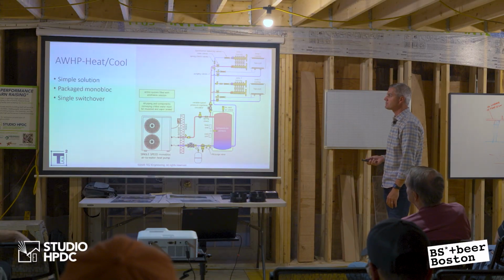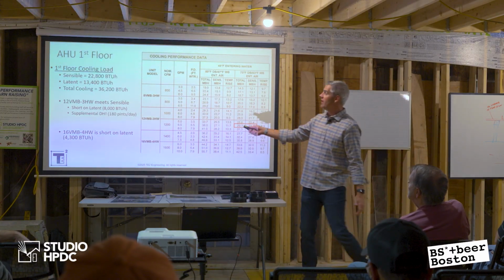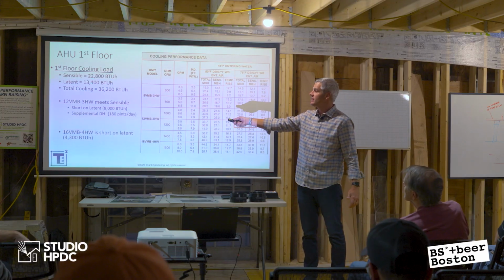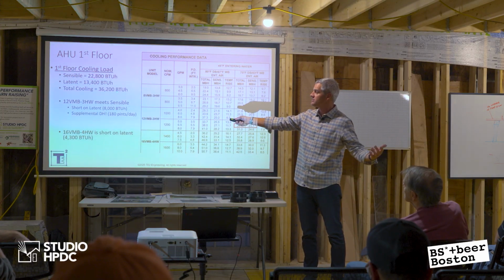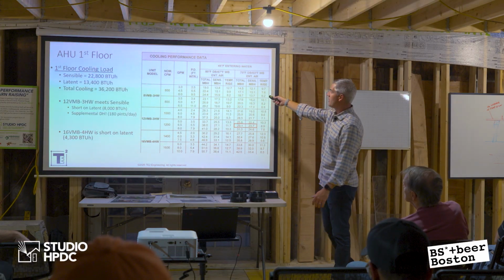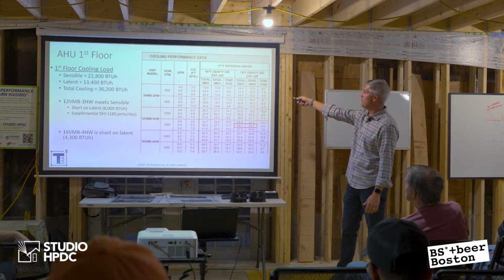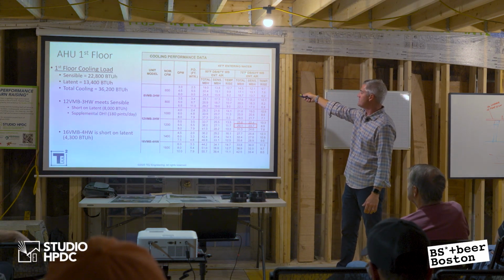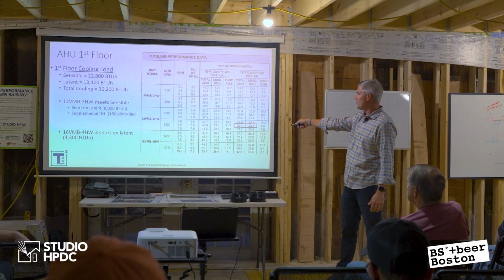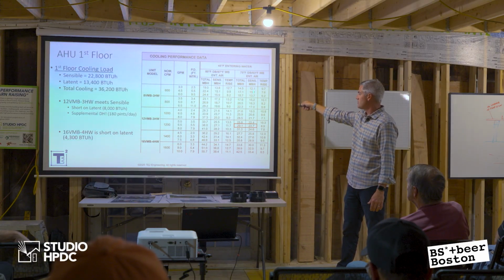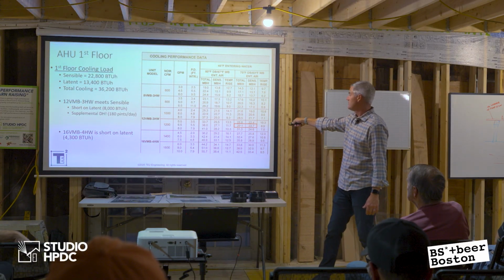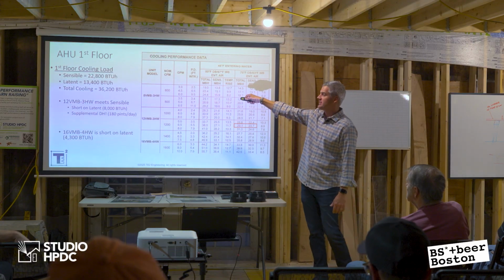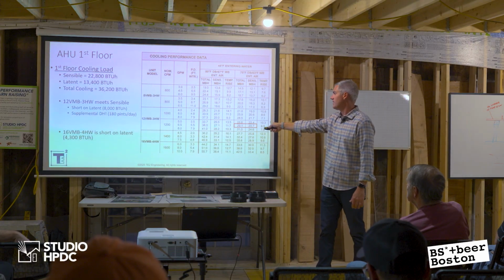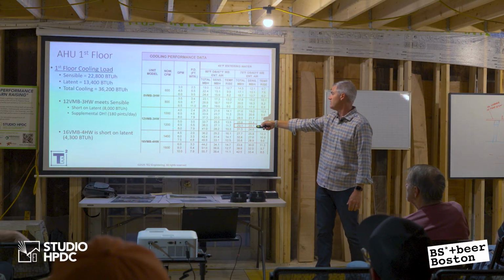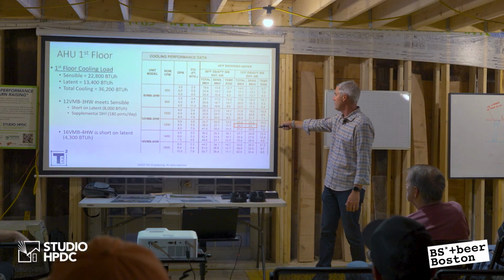Great point. Okay, so for that first floor air handler, here's my sensible load, here's my latent load, here's my total cooling. It's about 3 tons of total cooling. I go to the cooling performance chart, look at my unit, 45 degree entering water temperature, 75 degrees. Total cooling 29,000, sensible cooling 23,000. 23 meets my sensible load. That's 1,200 CFM on a 3-ton unit with 6.5 GPM of water flow.